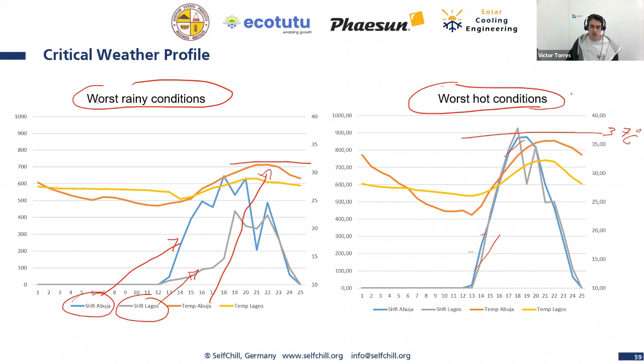What can we do? We take the very worst case scenario - high ambient temperatures and low radiation, which will typically never happen, but this is for us now the worst case scenario for our cold room. So our worst case scenario has ambient temperature here in black, going to 37 degrees in the day, down to 22 degrees at night, and the global radiation will be around 2.3 kilowatt hours per day. As I told you before, you won't find a worse day than this, so it is not necessary to consider zero solar radiation because you always have a certain amount - in your country it's 2.3. This is the worst case scenario.